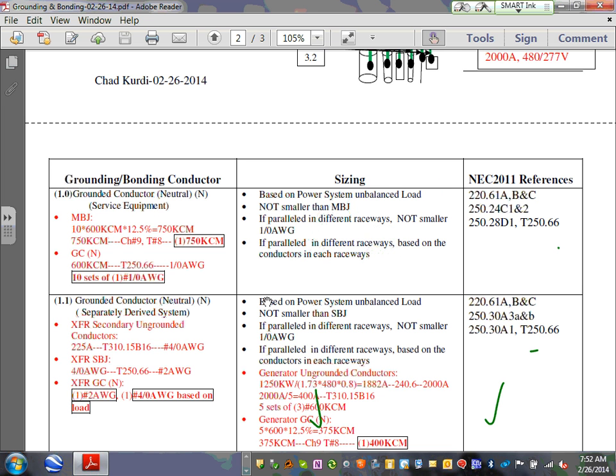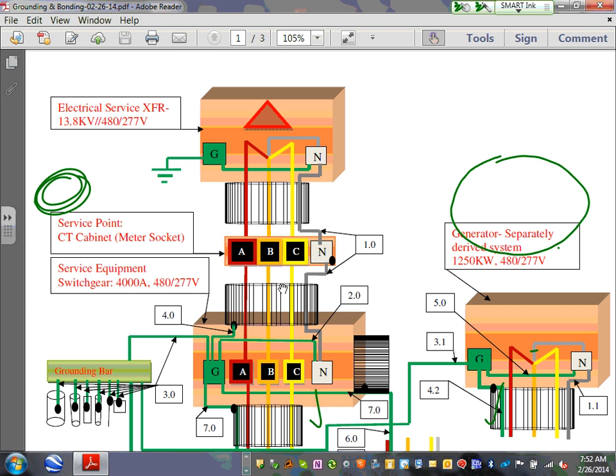And for those of you who doubt your friend Chad, here are all the references from 2011, Adam, that tell you to do so. Okay? Any comments, guys? Any questions? Everybody can see the connection between 1.0 and going all the way up to this conductor, which is called 1.0. That's the neutral, right? And why do we talk about the neutral when we're talking about grounding and bonding? Because the neutral is a grounded conductor. It's connected to the ground. Any comments, guys? Any questions? Comments, questions about 1.0?